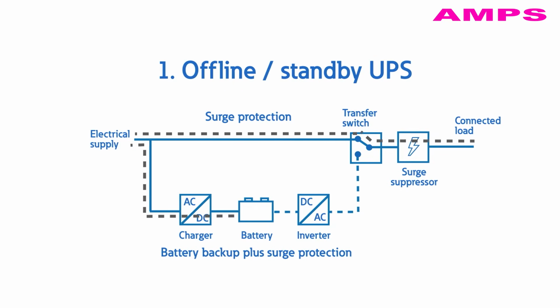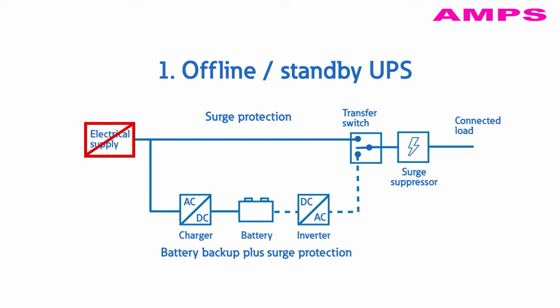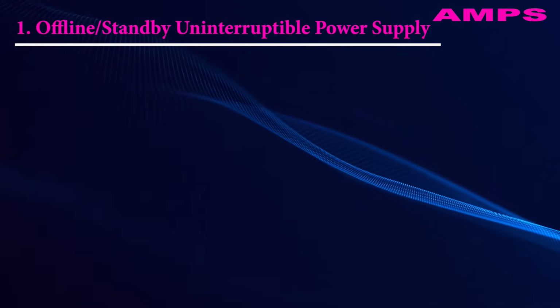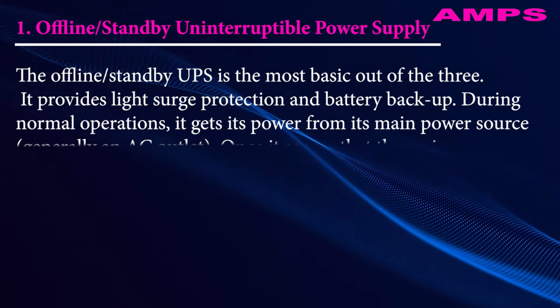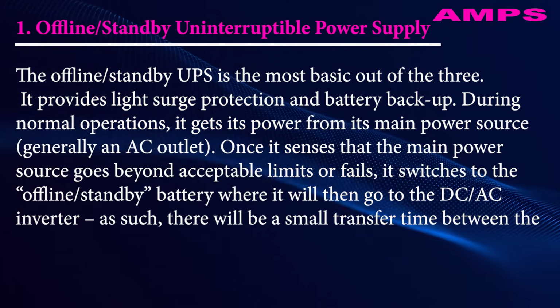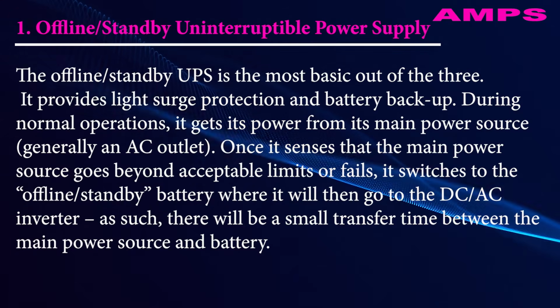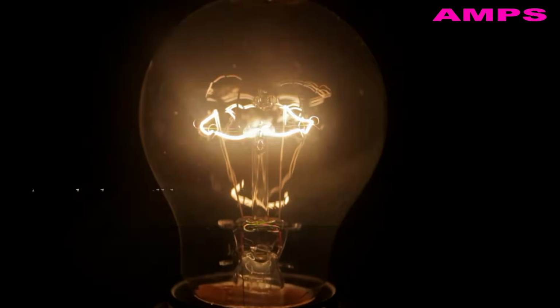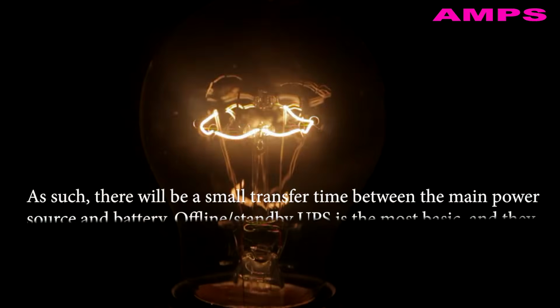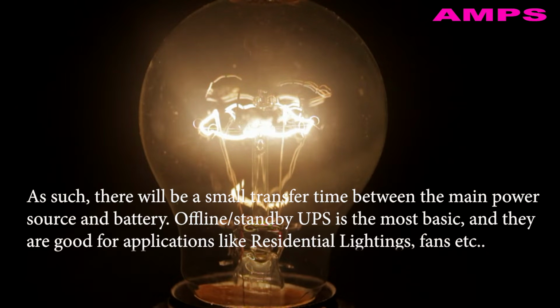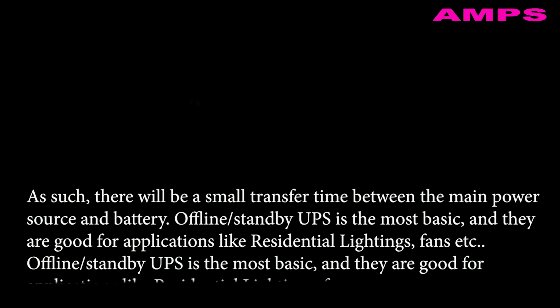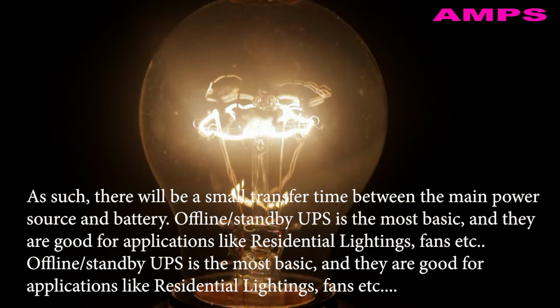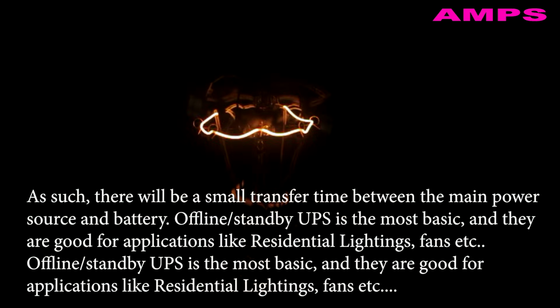It provides light surge protection and battery backup. During normal operations, it gets its power from its main power source, generally an AC outlet. Once it senses that the main power source goes beyond acceptable limits or fails, it switches to the offline or standby battery where it will then go to the DC or AC inverter. As such, there will be a small transfer time between the main power source and battery. Offline or standby UPS is the most basic, and they are good for applications like residential lightings, fans, etc.